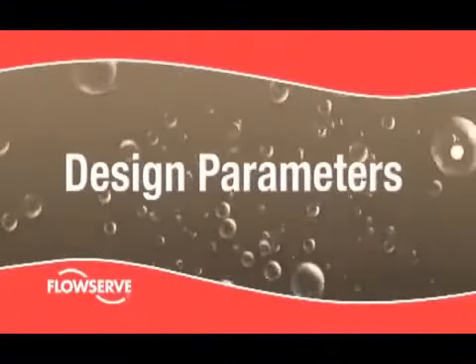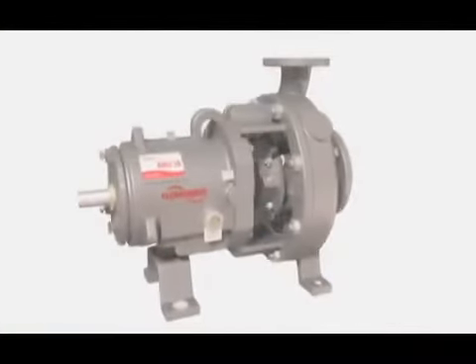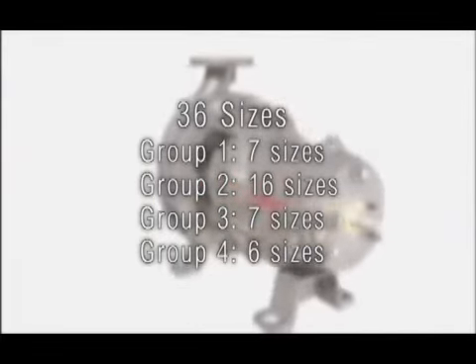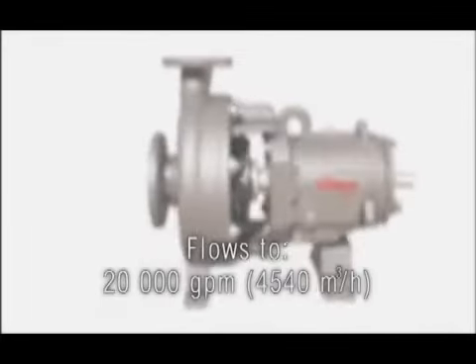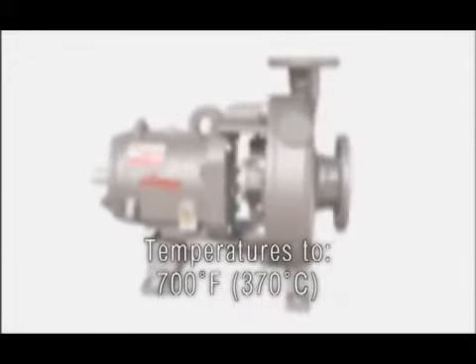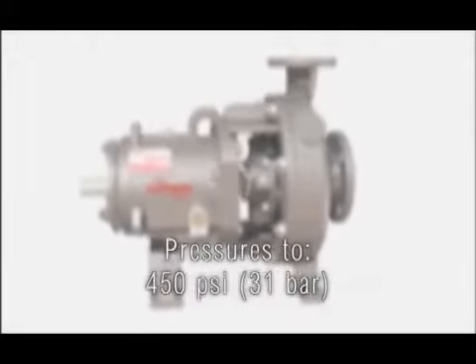Design parameters. The FlowServe Durco Mark III is available in 36 sizes, from Group I low-flow, high-head designs to Group IV high-capacity models. The Mark III handles flows to 20,000 gallons per minute, heads to 700 feet, temperatures to 700 degrees Fahrenheit, and working pressures to 450 PSI.